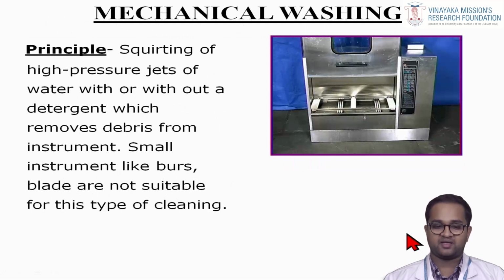Coming to mechanical washing, the principle is the squirting of high pressure jets of water with or without a detergent which removes debris from the instrument. Small instruments like burrs, blades are not suitable for this type of cleaning. So you prefer ultrasonic cleaning for those instruments.